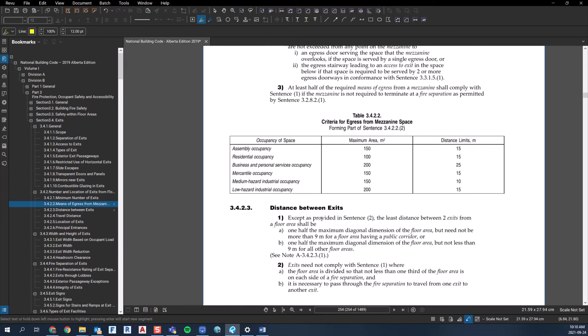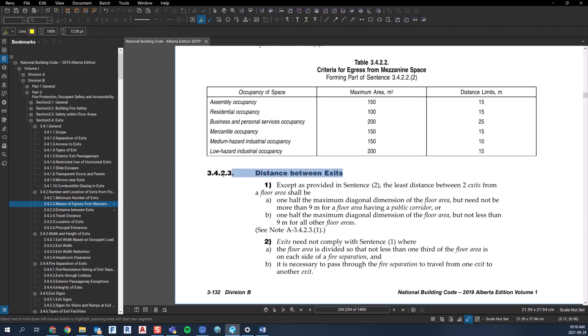Section 3.4.2.3 covers the distance between exits. We've determined we need at least two exits, so now let's read this section — it tells us how far apart those exits need to be from each other. It's pointless to have exits right beside each other; the intent is to ensure you have a choice of exits so that if a fire is on one side of the building, you can go the other way. The code gets specific about how far apart they need to be.